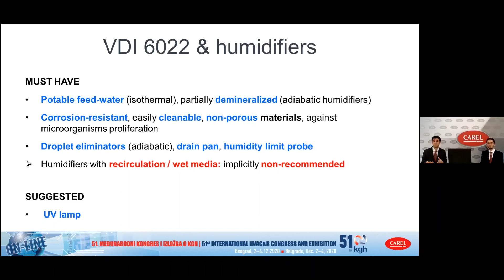Regarding the service, we know from VDI 6022 that isothermal humidifiers are intrinsically safe, so they can be used everywhere, also in operatory theaters, where the conditions must be stable and top hygiene. Why? Because the steam is normally at 100 Celsius degrees and kills all the bacteria and viruses inside the water.